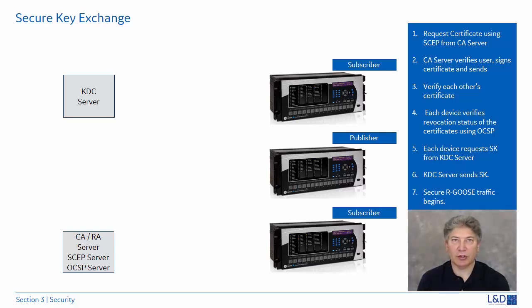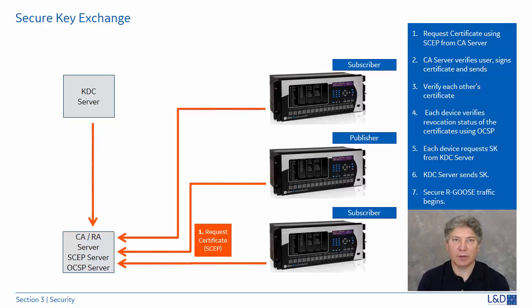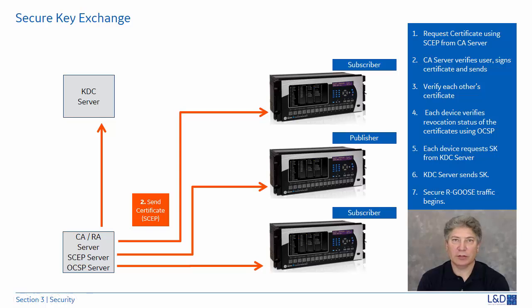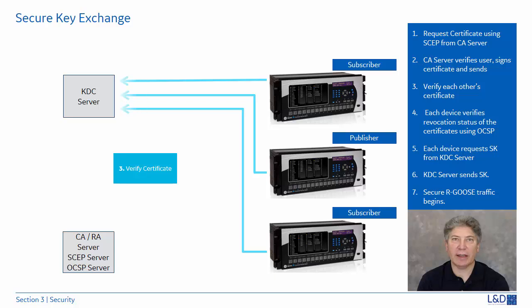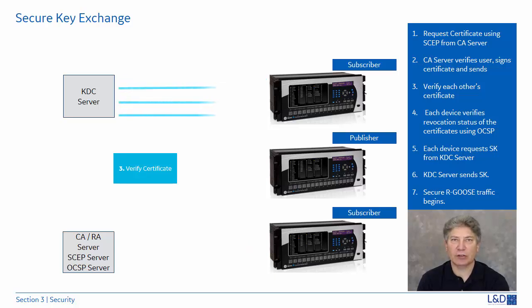Here is a simplified sequence of events to establish secure communication among routable GOOSE publishers and subscribers. There are two major exchanges: certification, used to authenticate all devices exchanging keys, and security — the distribution of symmetric keys used by the publisher and subscriber for signature and encryption. Step one: devices dedicated to obtaining a certificate request an X.509 certificate from the Certificate Authority using the Simple Certificate Enrollment Protocol. Step two: the Certificate Authority verifies the users, signs the certificate, and sends it to the devices. Once the certificate is obtained, the publisher or subscribers establish a connection with the KDC server using the GDOI protocol, share their certificates with the KDC server, and request the KDC certificate. The KDC and the devices then verify each other's certificates.